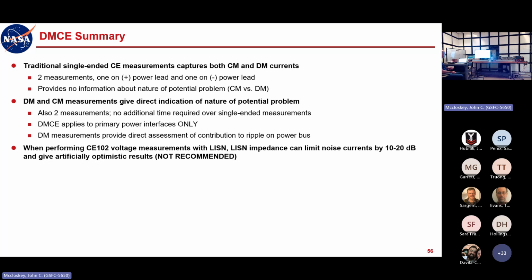If I get skewed results, I will always take a false failure over a false pass, because a false failure forces me to look at something. And if it turns out to be an exaggeration of the measurement setup, then I have to deal with that and come to some resolution of it. A false pass, oh, la-di-da, I'm good. And then something bites me at system level. And I don't like getting bitten at system level, and my management doesn't either.